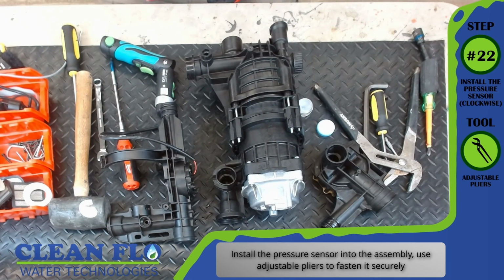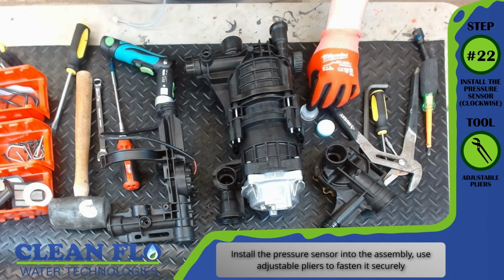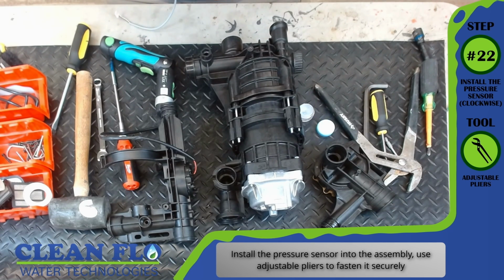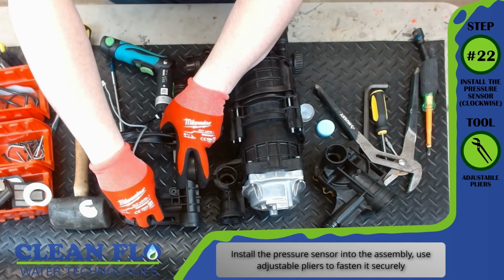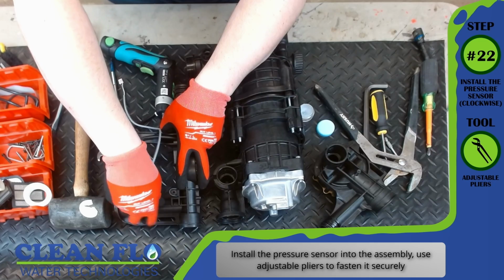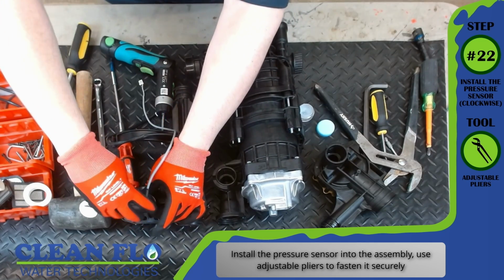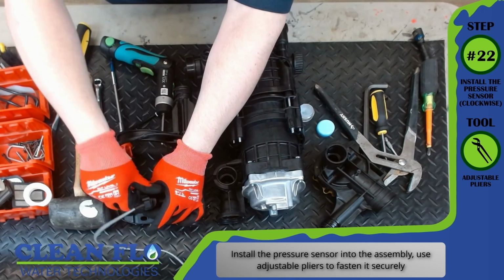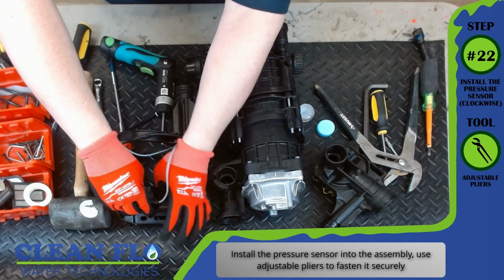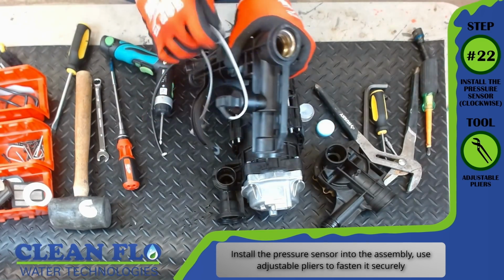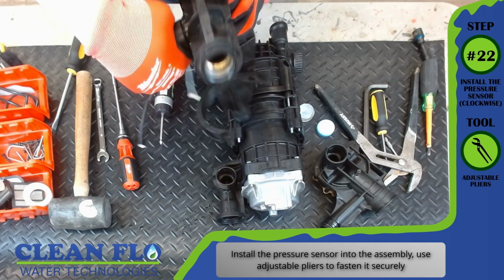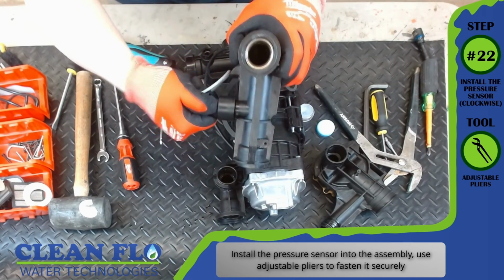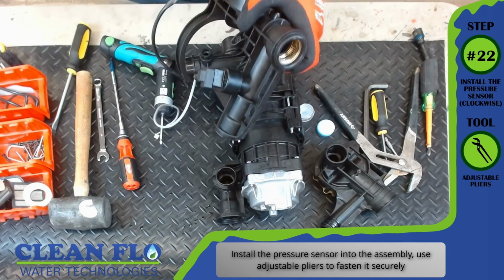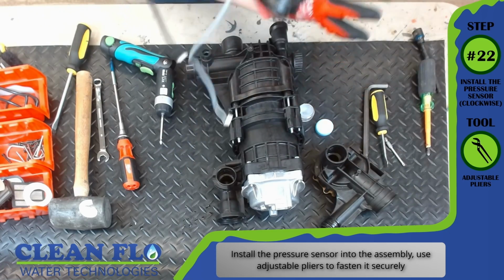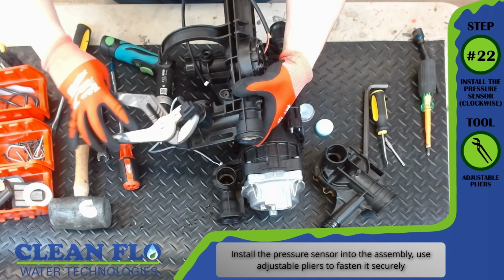Step number 22, install the pressure sensor clockwise. Tool, adjustable pliers. Install the pressure sensor into the assembly. Use adjustable pliers to fasten it securely. Use the silicone lubricant to make sure the O-rings are properly lubricated. Screw in the pressure sensor by hand, and then if need be, use your final 1/8 turn with adjustable pliers.